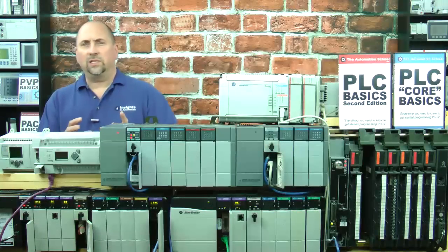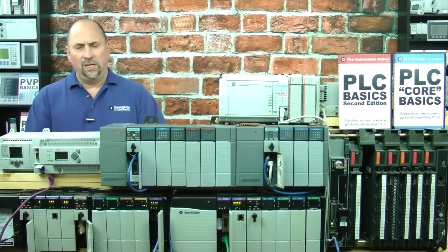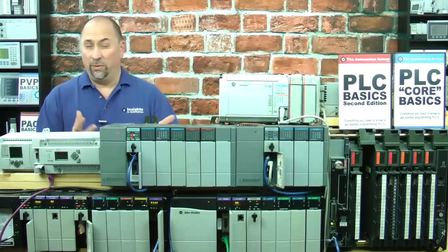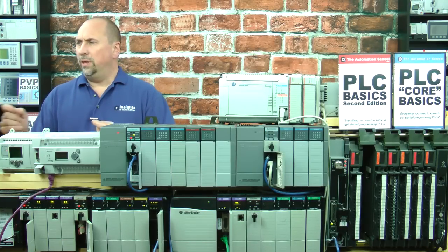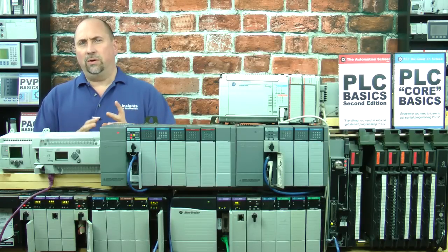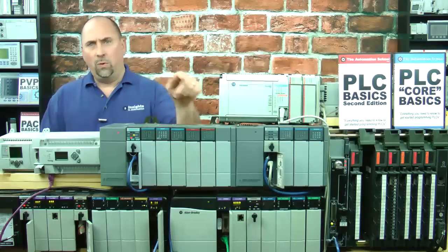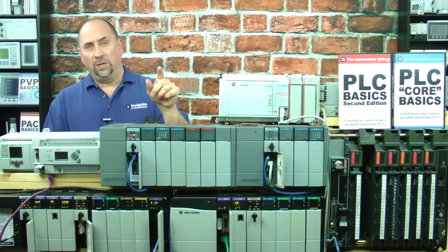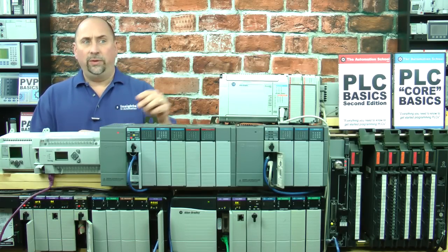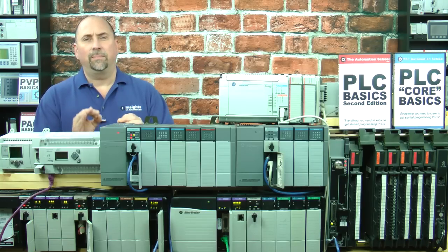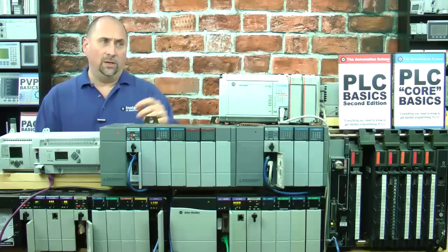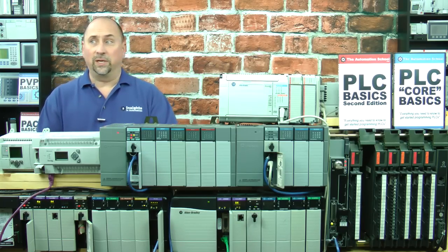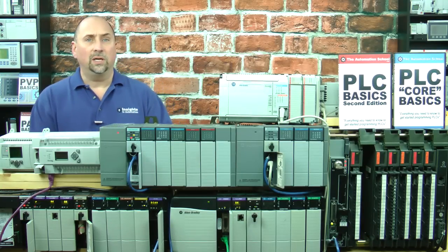Now, if it's not successful for you, it could be a couple of different things. Occasionally, you'll get a bad COM port on the unit or a bad cable, although that's very rare. More than likely, if you have a problem with this auto configure, it's going to be that the port isn't set up for the default DF1. If that happens, you can actually just press the button underneath the cover there to set it back to default comms. You'll get the default comm light that will come on, and that'll set it back to DF1 full duplex, which is what we're trying to use here to communicate to it.